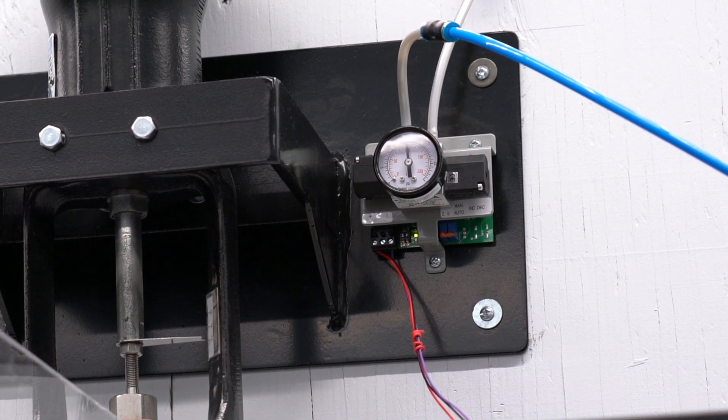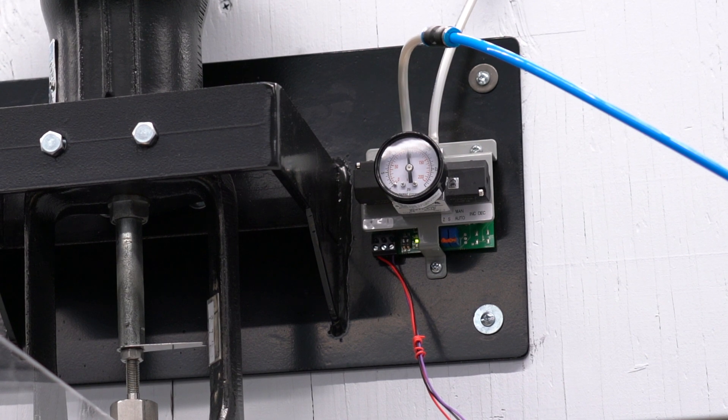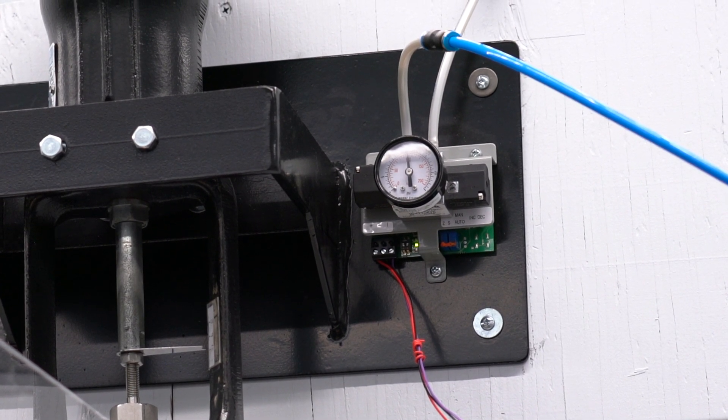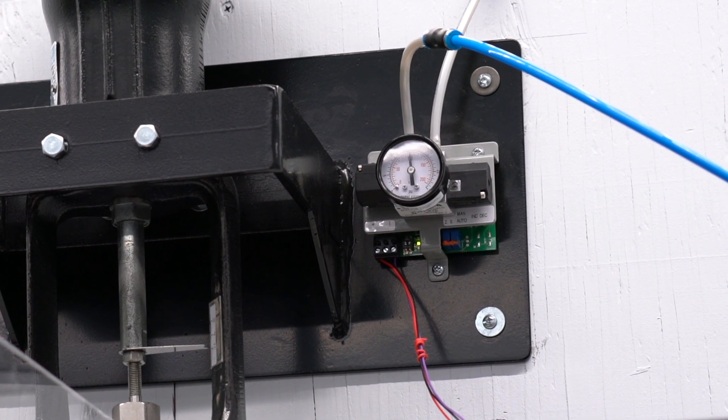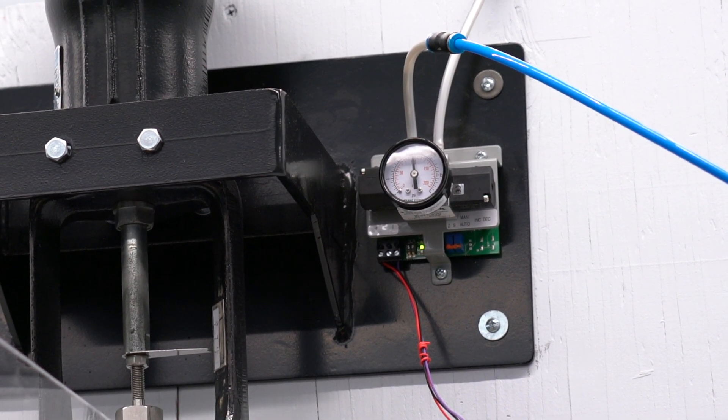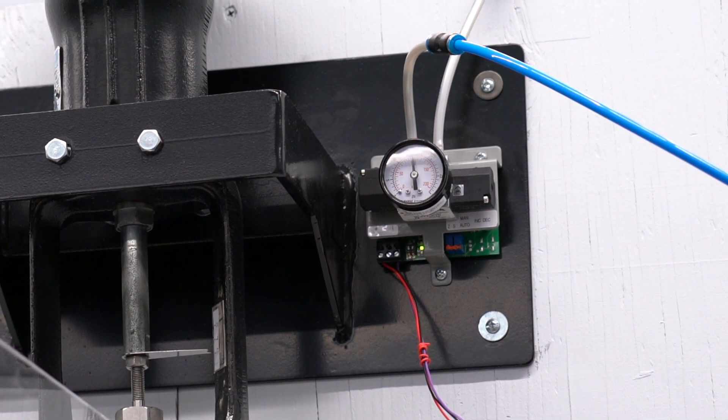The reason it's not 0 psi is that a lot of pneumatic systems always start at 3, because that way we can detect if there's a leak in the system. It'll go to 0 psi and not be at 3. So it's 3 to 15. Right now the gauge is showing me 15 psi.